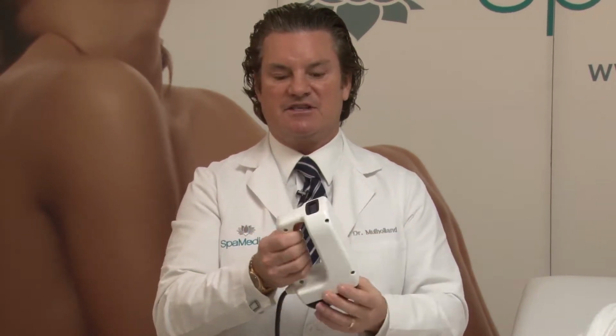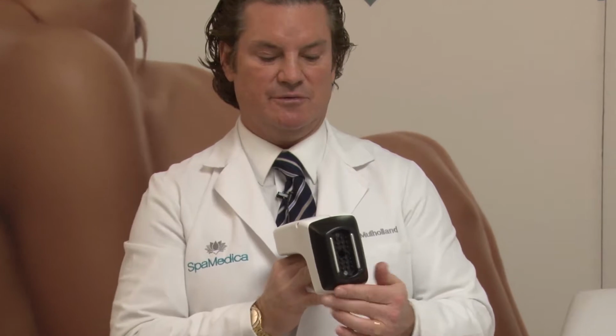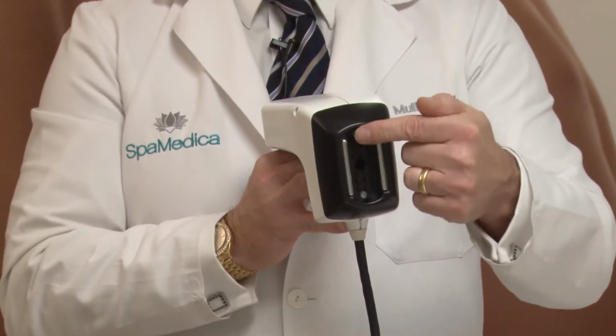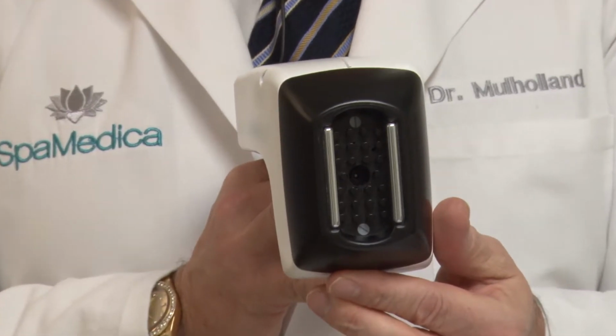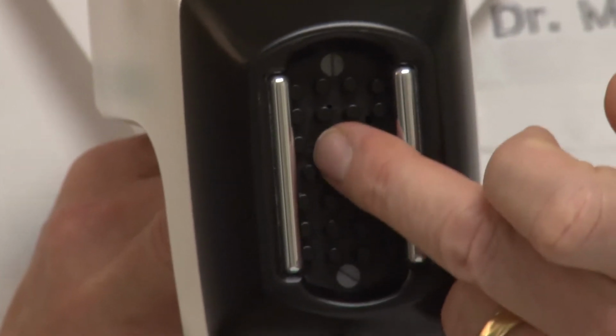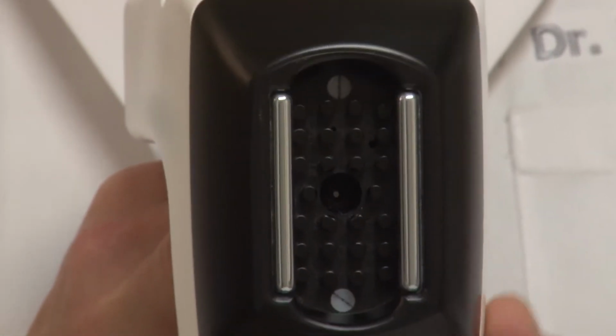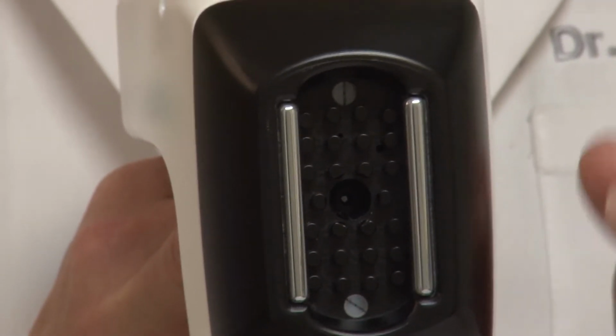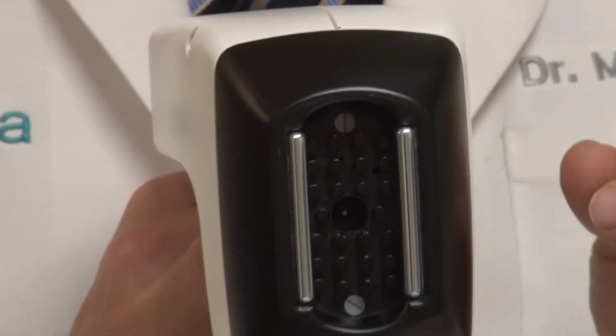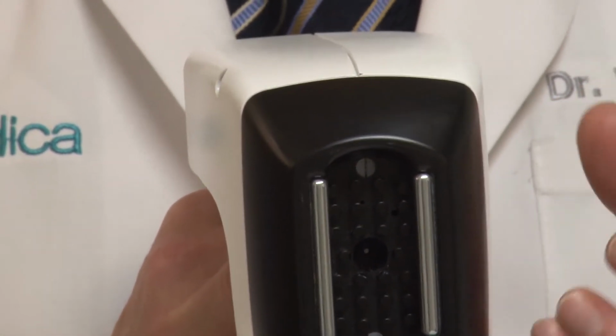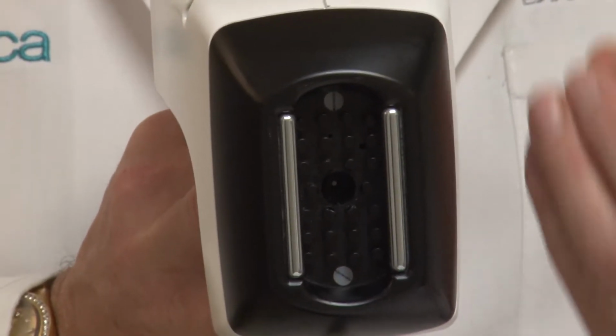All the cool stuff's in the applicator. The high voltage pulse generator, the display that gives you the epidermal temperature at all times, and it cuts it off at the endpoint that you set, 42 to 44 degrees. The undersurface, or the active element, is, if you zoom in, 2 RF electrodes, which is suction coupled. There is no optical component to this. There are little plastic stalagmites at the top that prevent the soft tissue from being sucked and obliterating the central port. The central port measures epidermal temperature at all times. It measures suction force, and it measures tissue impedance, high and low, and it will cut off around that, allowing a completely thermally controlled RF delivery.